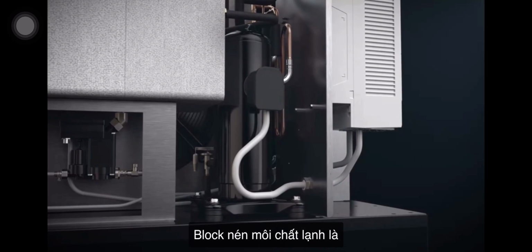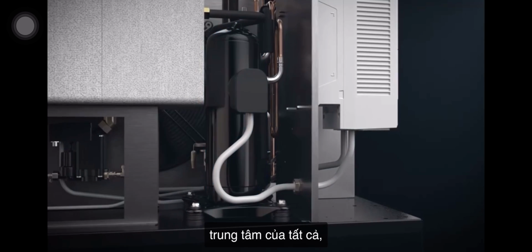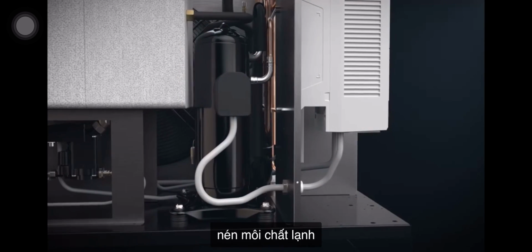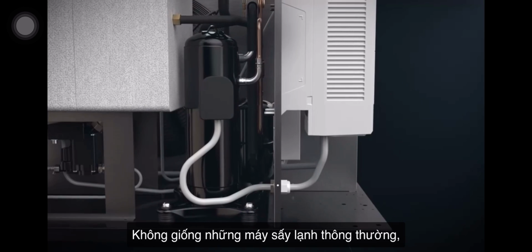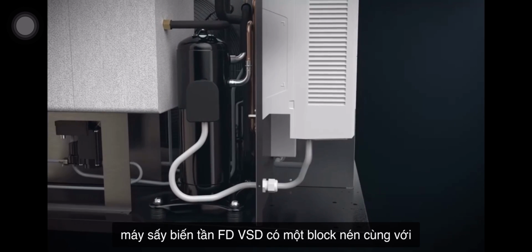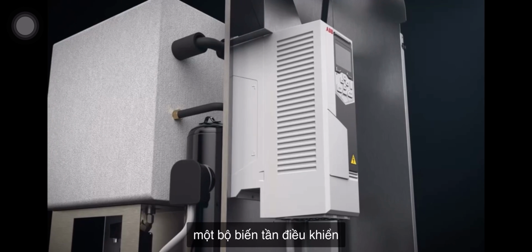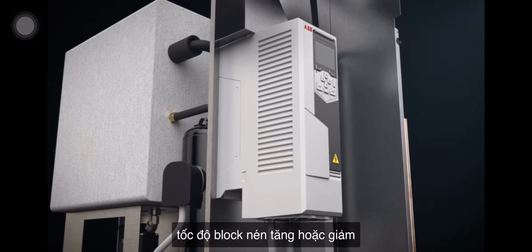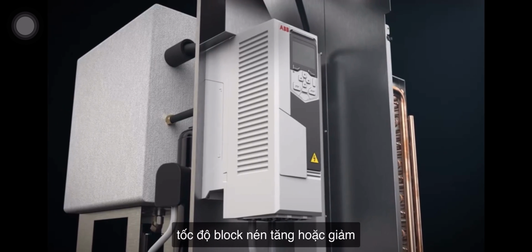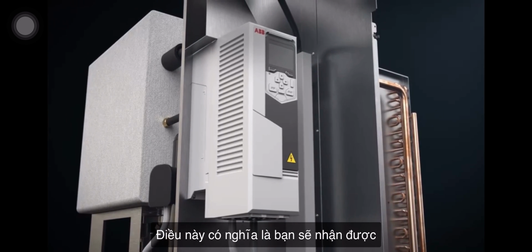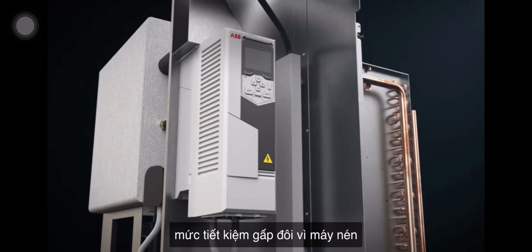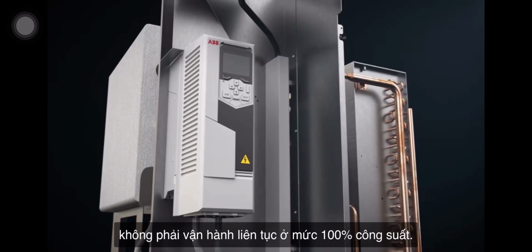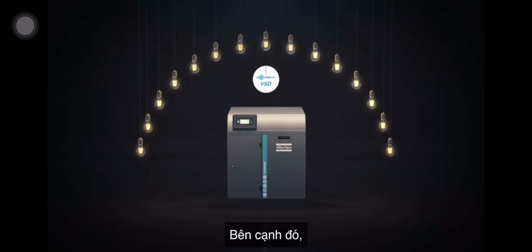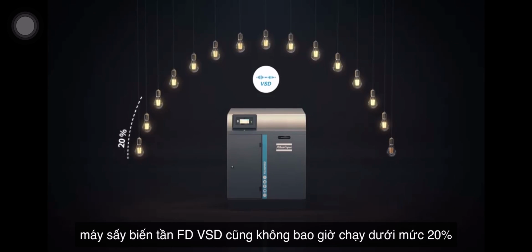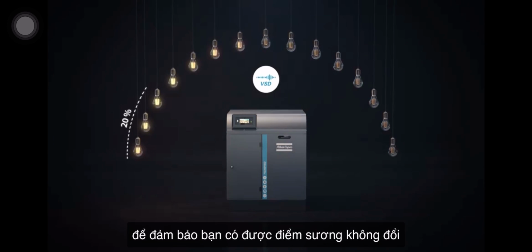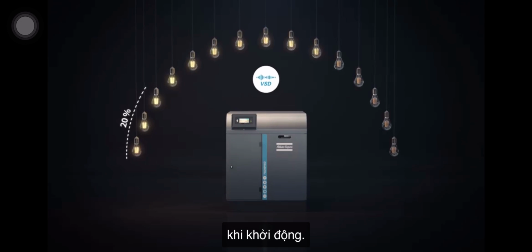The refrigerant compressor is at the heart of it all, compressing the gaseous refrigerant to a higher pressure. Unlike typical refrigerant dryers, the FD has a VSD compressor with an inverter that controls the speed of the compressor up or down to match your compressed air need. This means you enjoy double-digit energy savings as the compressor is not continuously running at 100%. In addition, the FD VSD also never runs below 20% to ensure you get a constant dew point at startup.